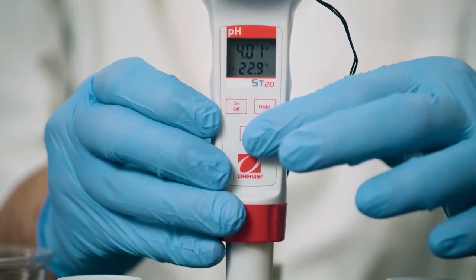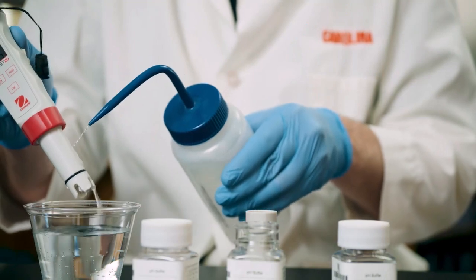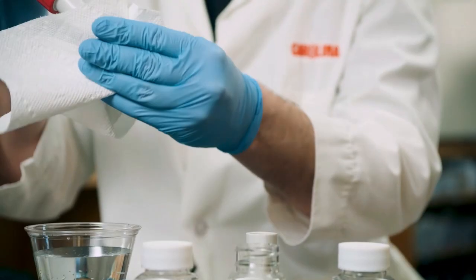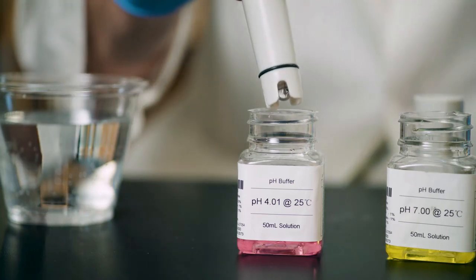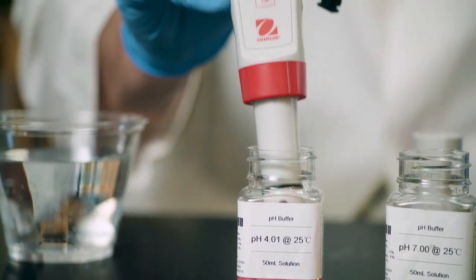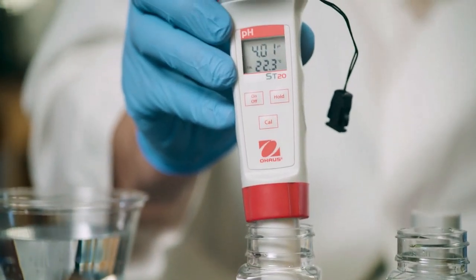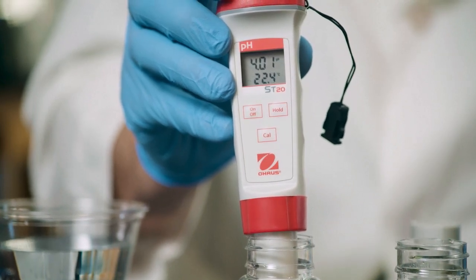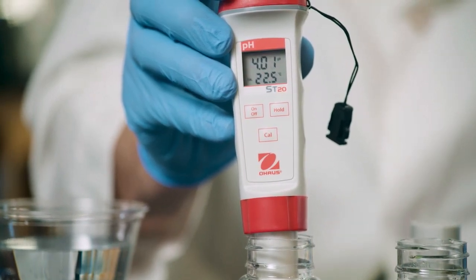The calibration point has been collected. Now rinse the electrode with distilled water. Repeat this process with the 4.01 and 10.01 buffer solutions. Recall that this is a 3-point calibration. Place the pen meter into the 4.01 buffer solution and wait until Cal begins to blink.